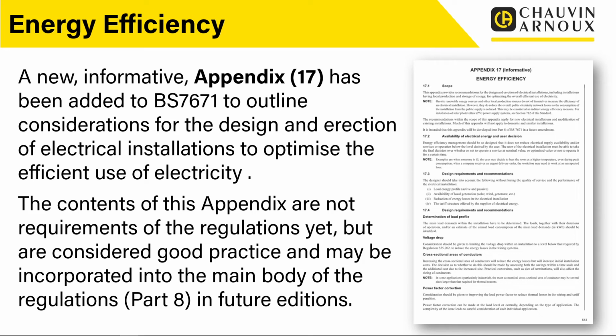So that's an important point. I don't know if you're aware of that, but where you've got an appendix that says it's informative, or anything in the regulations that says it's informative, it's not actually part of the body of the regulations. It's not a requirement. You don't have to do it. It's there for information. It's informative. So at the moment, Appendix 17 and the contents of it are just there for information. They're not actually requirements to comply with the British Standard, comply with the regulations.